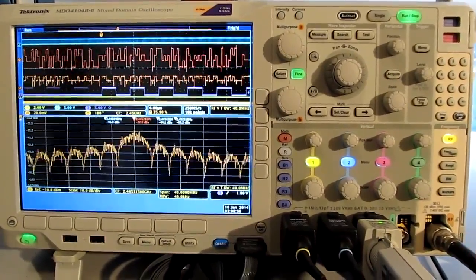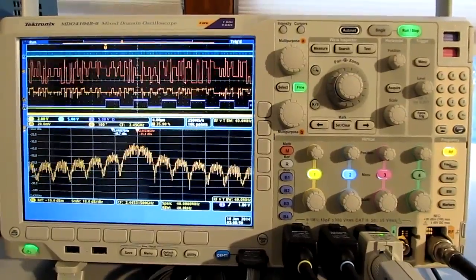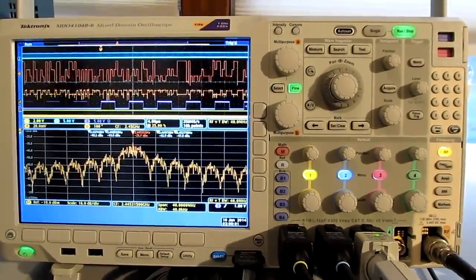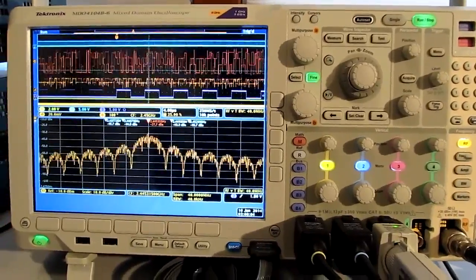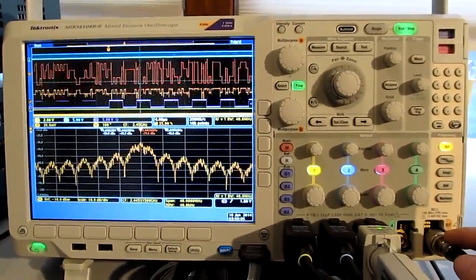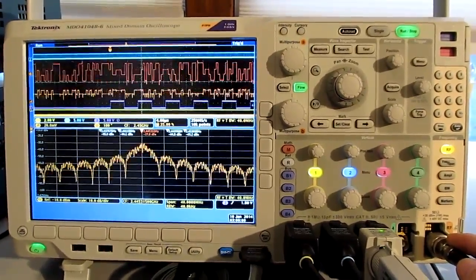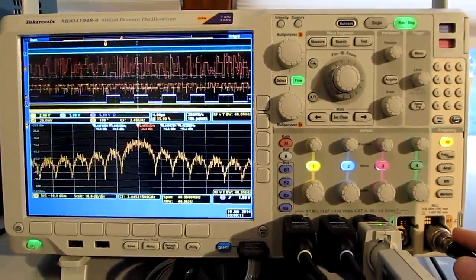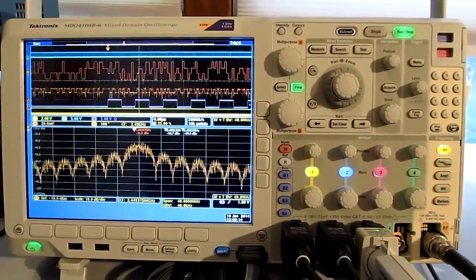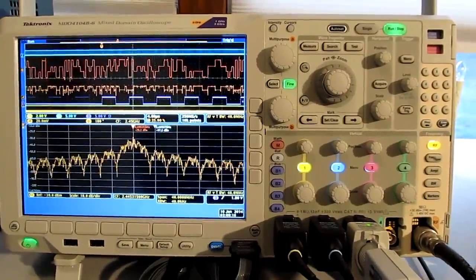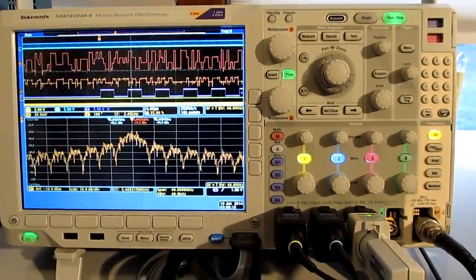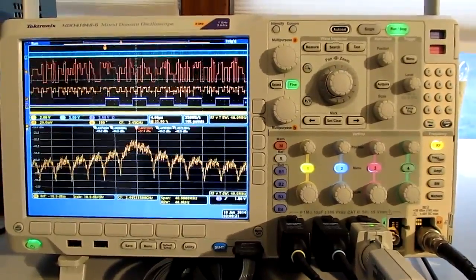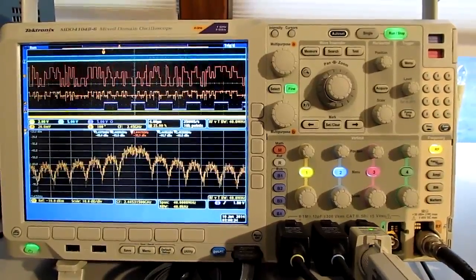But to me, there's a number of other user enhancements, but the most exciting one for me is a live link between the RF capture in the MDO and vector signal analysis that can be run on an external PC. And what that does is it turns the MDO now into a wideband, 1 GHz wide vector signal analyzer at a very low cost. So let me show you what I'm talking about with that.